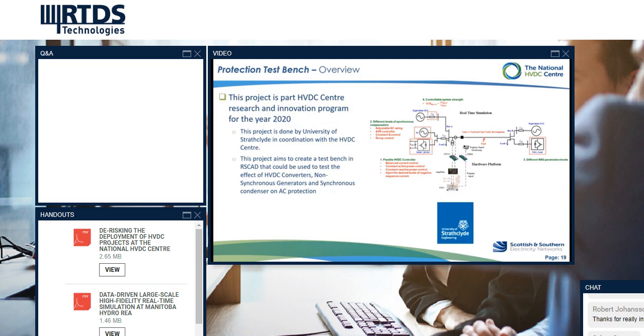The main aim of this project is to develop an RTDS test bench that could be used to test the effect of converters, HVDC converters, synchronous condensers, and non-synchronous generators on AC protection. You can see the overview of the test bench in the diagram on the right. The main components of this test setup are the MMC converter, synchronous condenser, voltage sources, the AC line, its loads, and the non-synchronous generator, which are all modeled in RSCAD.